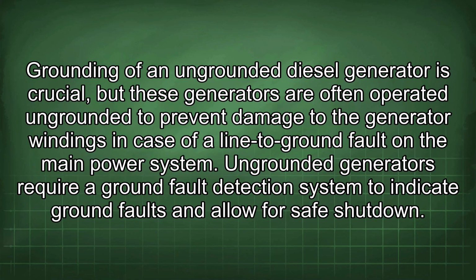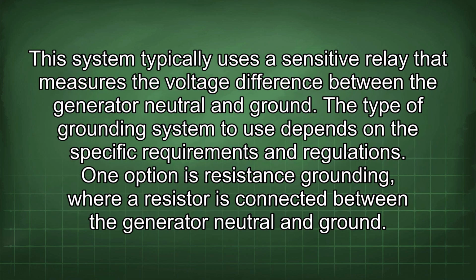Grounding of an ungrounded diesel generator is crucial, but these generators are often operated ungrounded to prevent damage to the generator windings in case of a line-to-ground fault in the main power system. Ungrounded generators require a ground fault detection system to indicate ground faults and allow for safe shutdown. This system typically uses a sensitive relay that measures the voltage difference between the generator neutral and ground.